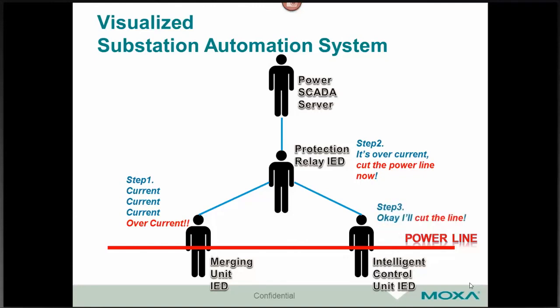It says, okay, you better cut the line. And so they say, okay, I'll cut the line, and they send back to the protection relay, I cut it so that you know. Then the protection relay says, okay SCADA, I'll let you know with an alarm, because I had to do these things. So now you're aware of what I did while you were sitting at your desk. So what does that translate to?